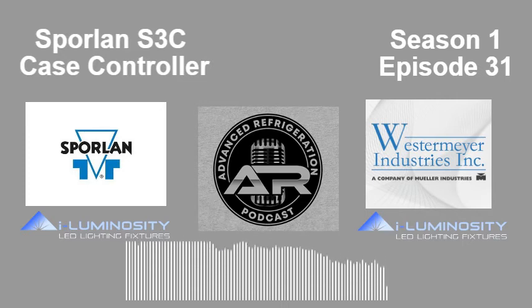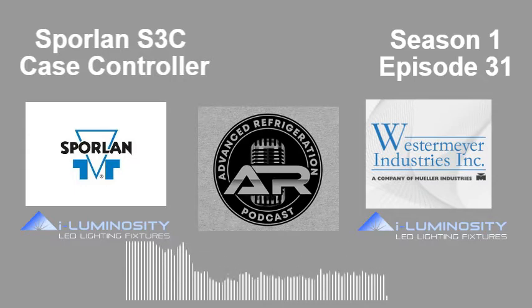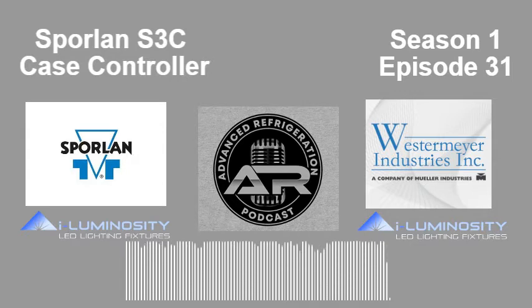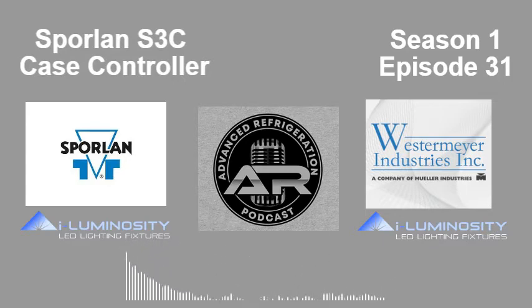Yeah, if you have the availability to put a specialized step in there, then as long as it's linear, you should be good. But you've got choice. Predominantly, this is going to be a 2,500 step EEV that's going to go into place. Our old traditional CDS valves had almost 6,400, 6,500 steps, and one of the input parameters is number of steps. And that's one of those things that can be keyed in incorrectly as well.